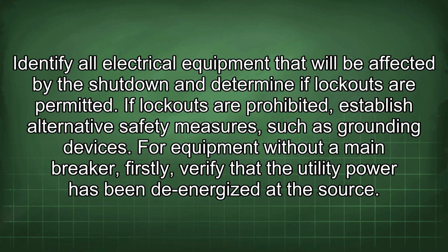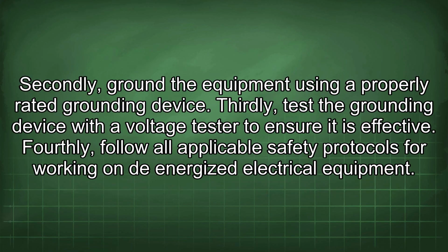For equipment without a main breaker, firstly, verify that the utility power has been de-energized at the source. Secondly, ground the equipment using a properly rated grounding device. Thirdly, test the grounding device with a voltage tester to ensure it is effective. Fourthly, follow all applicable safety protocols for working on de-energized electrical equipment.